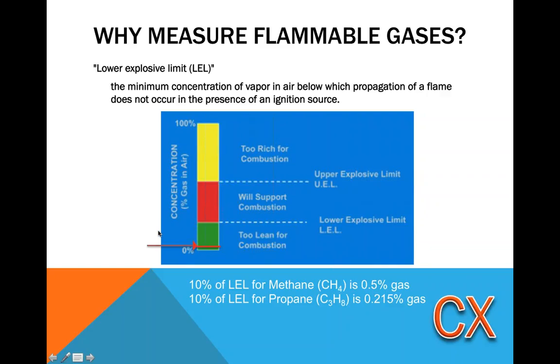And most of the devices you'll see limit the exposure to 10% of the LEL, and that would be for both methane and propane, which is a different concentration of gas because they are different chemical compounds. But it's well below the upper explosive limit, but it's a 10% factor of the lower explosive limit, is where most devices are going to sound off.